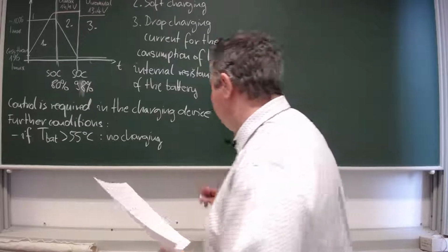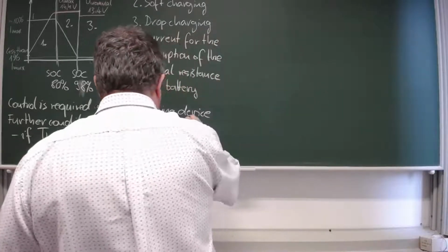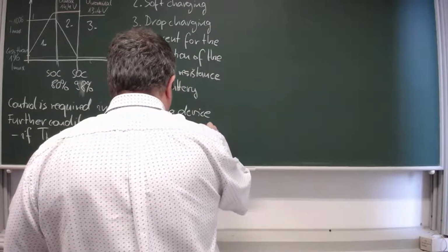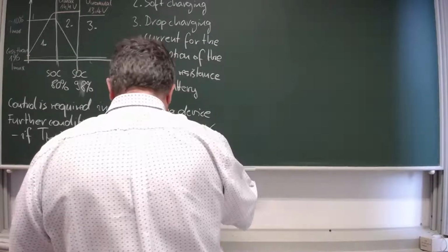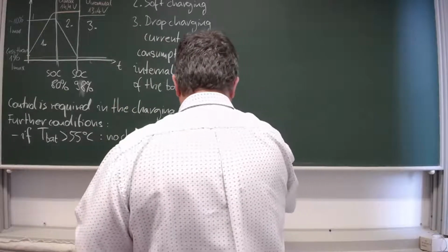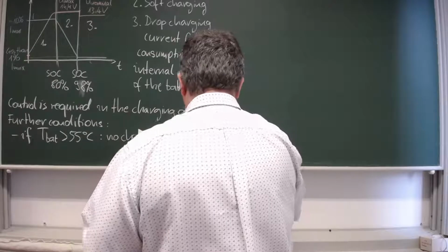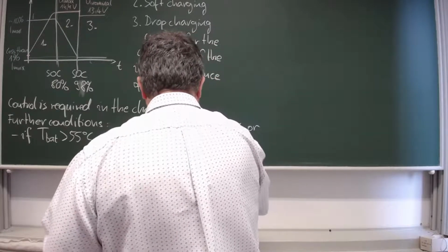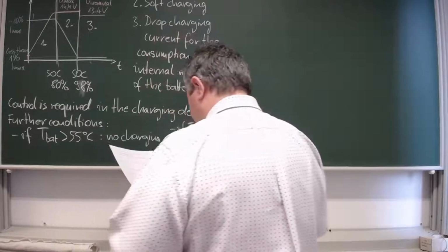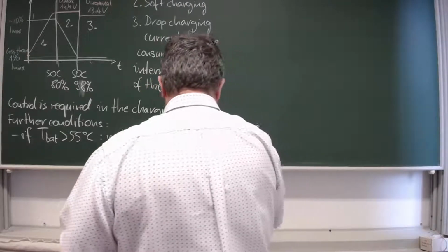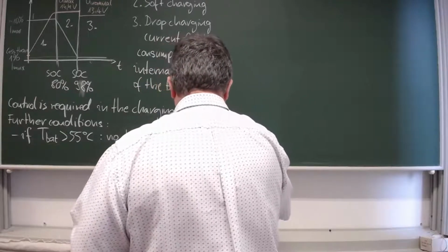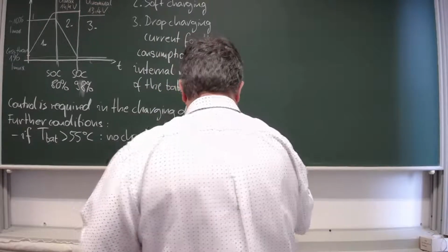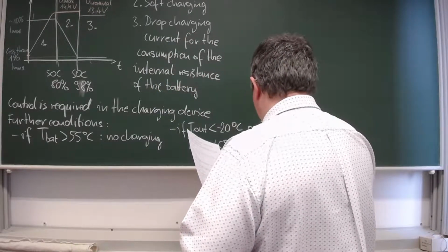And if temperature outside is smaller than minus 20 degrees Celsius, or temperature outside the battery is higher than 45 degrees Celsius, again, no charging.